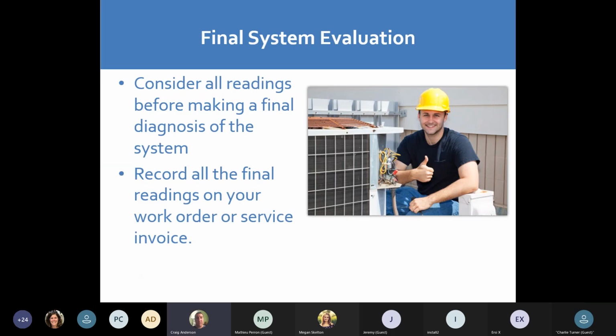So this is where you want to do your readings. You don't want to just throw your gauges on and allow yourself to maybe get in, we'll say, trouble the next time. Write down what you're doing. If you don't have an evaluation sheet made up, make one up. Write down what your pressures are. Write down the temperature it was outside that day, what your supply air temperature. Mark down all your readings.